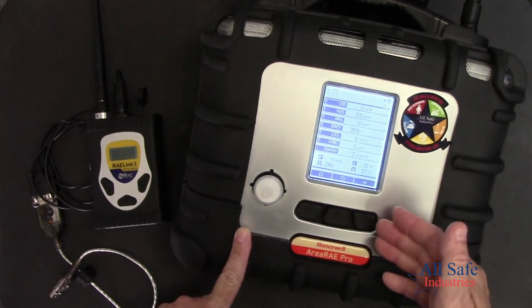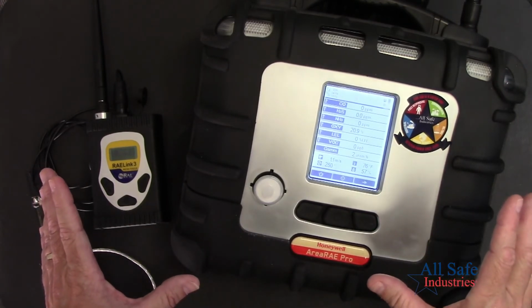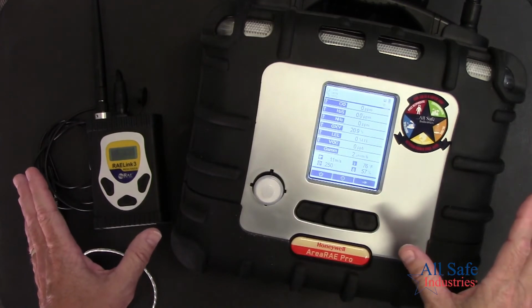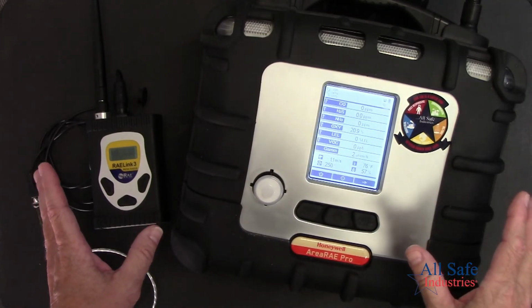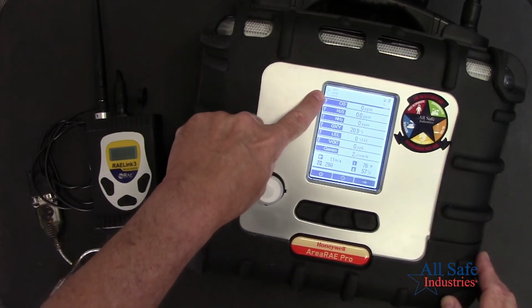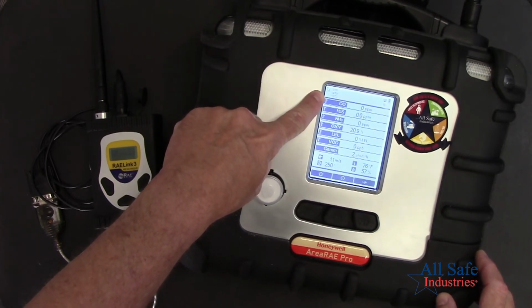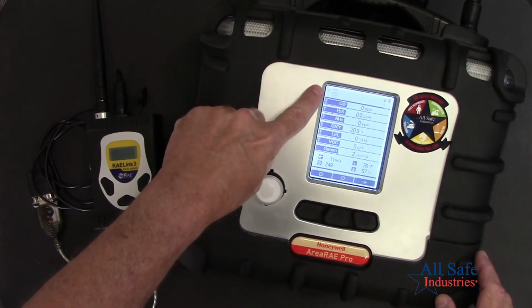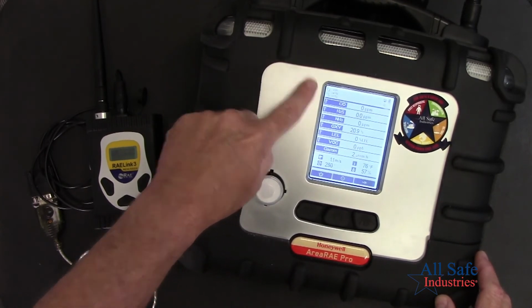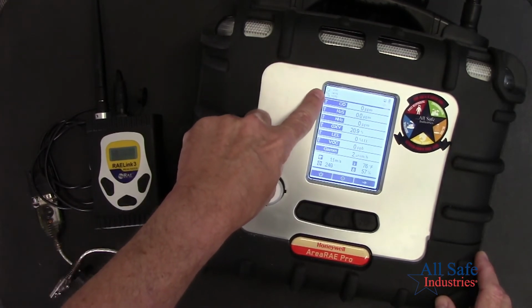So this is your main display screen. Again, if you're a current RAE Systems wireless user, then there's probably nothing that you need to set up. And so the step that you can go to is the last step, which is looking at this icon right here. This antenna icon with the 4 bars next to it, see how it's burning steady? That means it has connected to a host radio. So this AreaRAE is now talking with this RAELink 3 because that icon is burning steady.